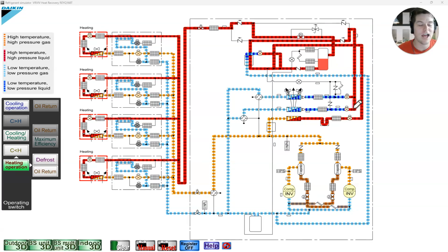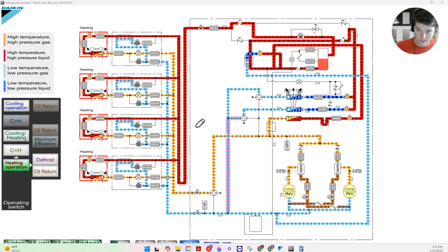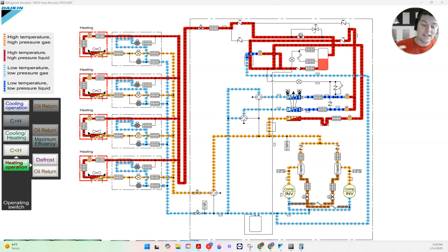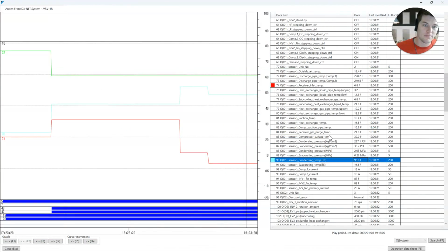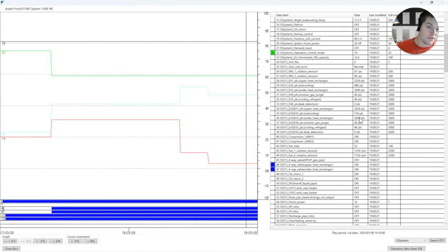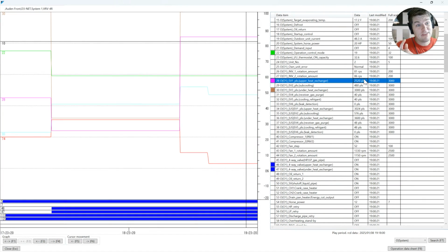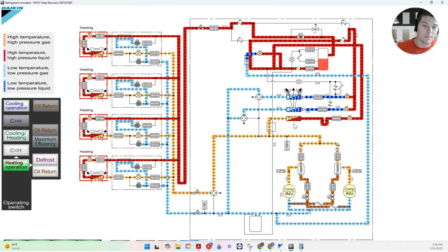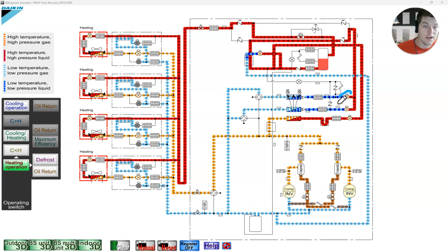Okay, let's just, you know what, because your mind's already rattling and you're probably like, no idea what's going on here. And you're going to quit this trade now because this just doesn't make any sense. Let's go a little bit further. Let's look at our outdoor expansion valves. What do we know about expansion valves? If they're wide open, they're not metering refrigerant and they're doing nothing. If they're closed, they're pinching off refrigerant. They're not supposed to be doing that. Why? Because they're getting too much refrigerant behind it. That's a problem. We got to look at that. So if we look at this, 2,520 pulses. I'm getting all fired up now. 3,000 pulses. This is wide open on my outdoor unit. Means I am not metering any refrigerant. So if I jump back over to my diagram and I draw you some more pretty colors, this is wide open.